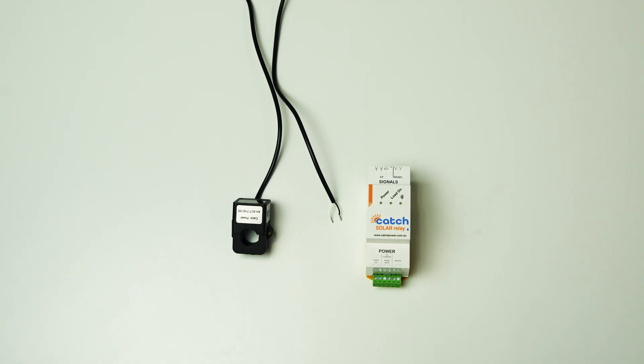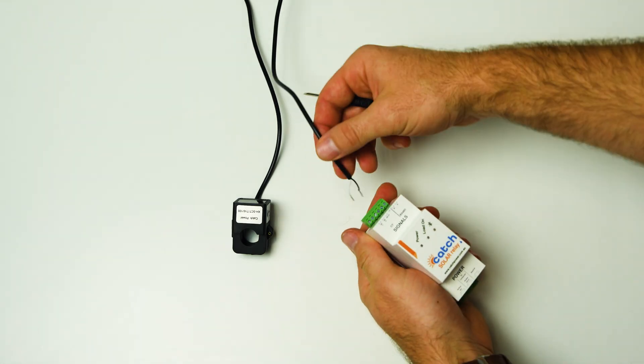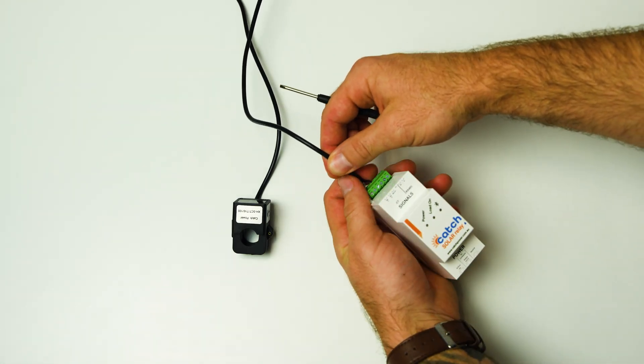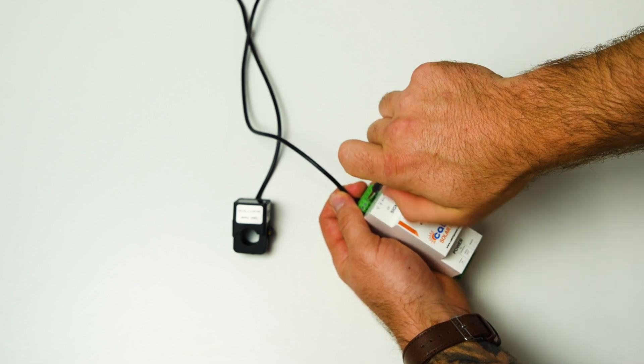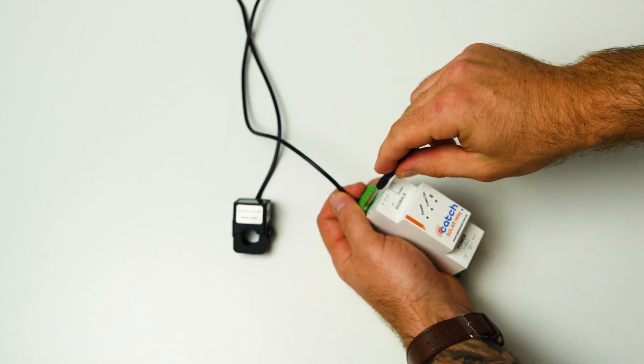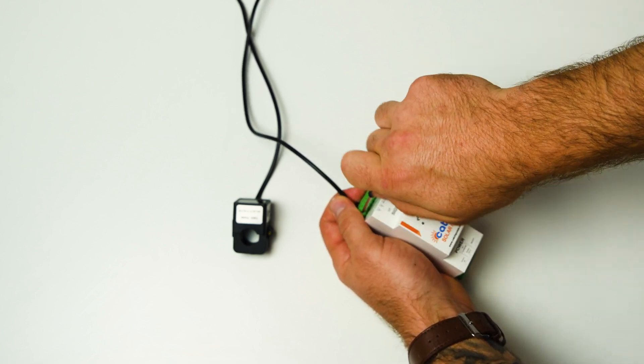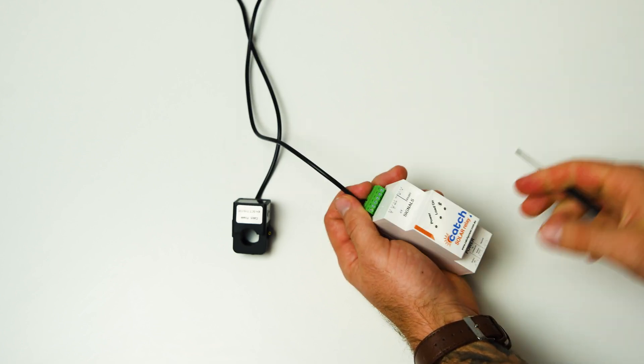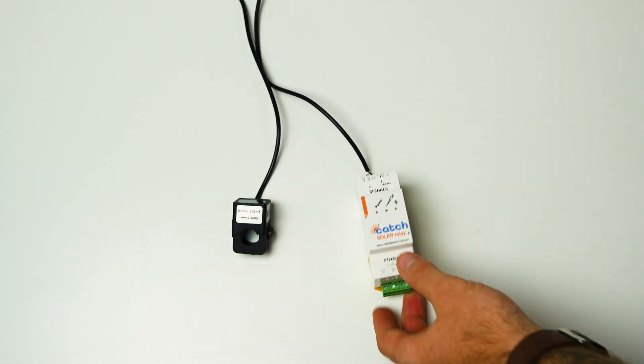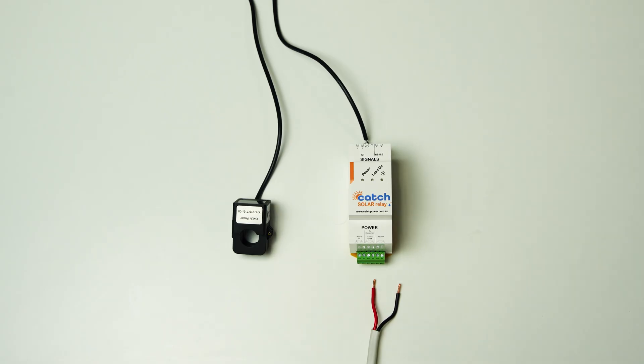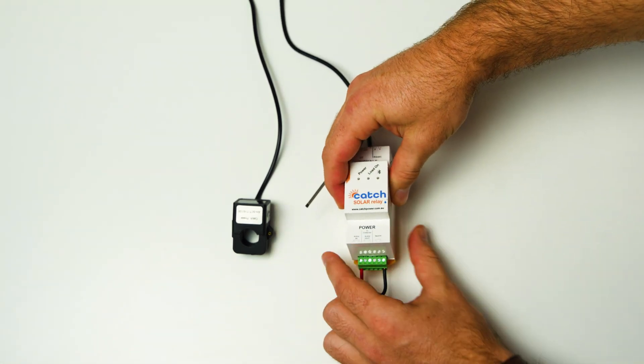Now we connect the CT into the top side of the relay with the white cable in W1 terminal and black into black. The AC connection is at the bottom of the relay with red into active and black into neutral.